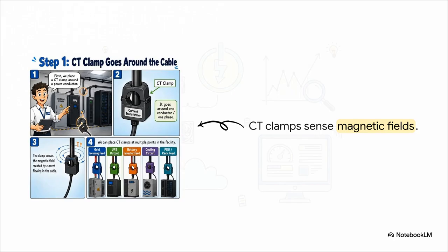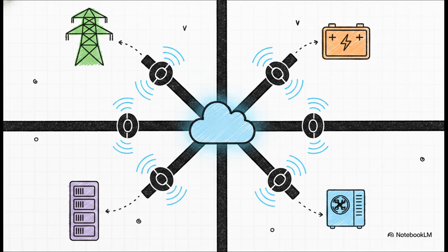It's brilliant. And because these clamps are completely non-invasive and so easy to install around existing lines, they are mapped all over the facility. They provide live, granular visibility at literally every critical junction. We are talking about mapping clamps on the grid incoming feed, the UPS output, the battery inverter feed, the dedicated cooling circuits, all the way down to the PDU or rack feed. This creates a highly dense web of sensors, constantly feeding real-time energy data back to the centralized software.